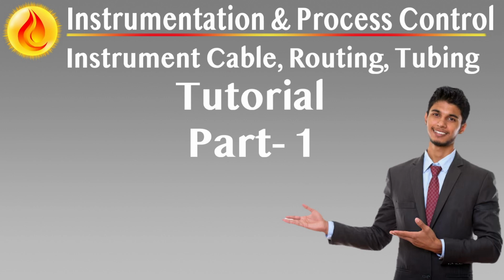Special application cabling. Non-standard instrumentation, e.g. flow meters, analyzers, machine diagnostics, often demand unique cabling and termination practices. Manufacturer guidelines shall govern selection, shielding, routing, and earthing. In select cases, bypassing junction boxes and MDFs in favor of point-to-point runs may be necessary.